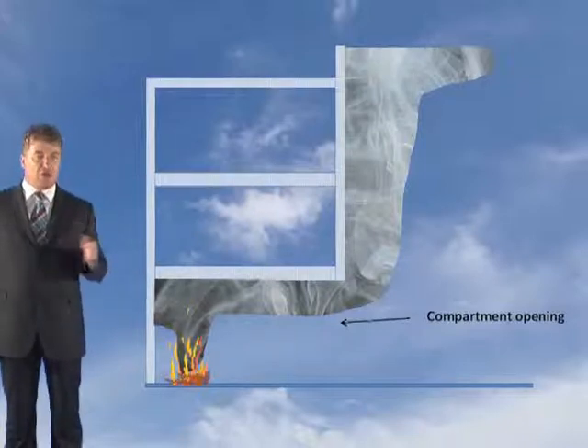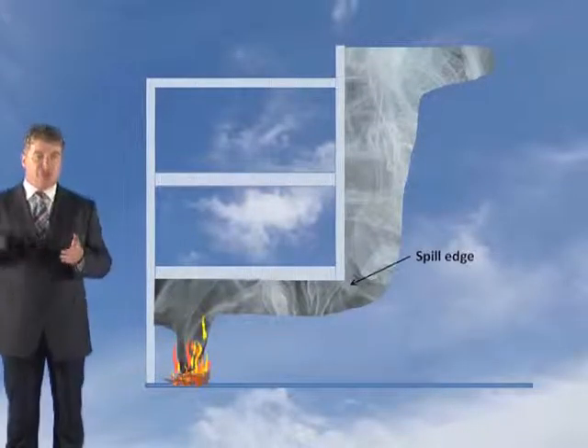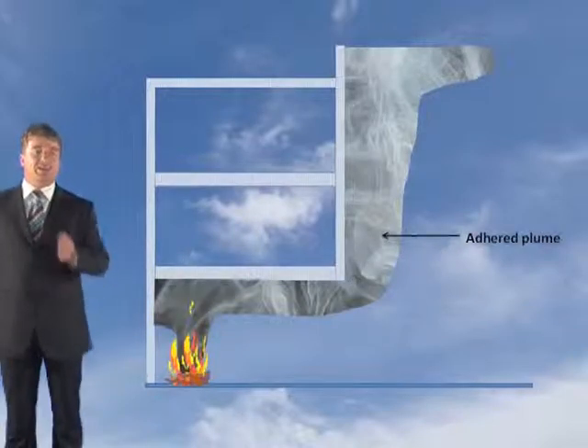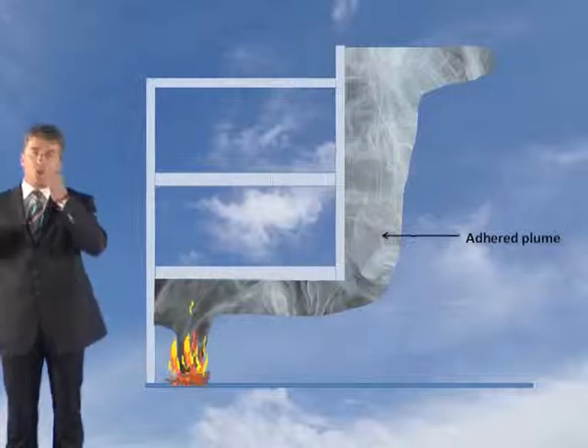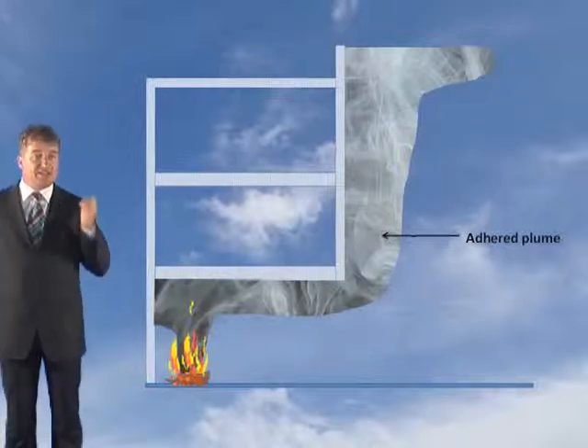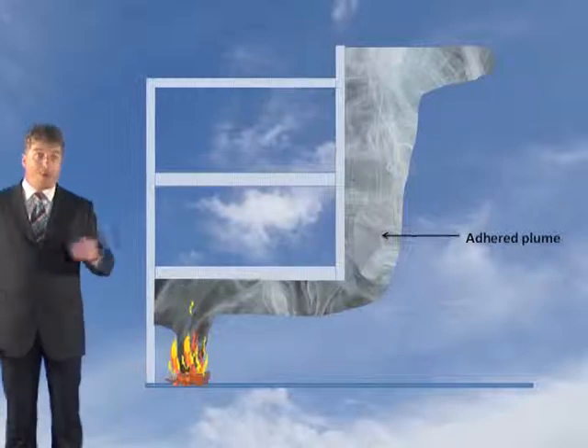Now the smoke layer below the compartment opening will then rotate at the spill edge — in other words, it comes out of the opening — and this plume will then adhere to the vertical wall as it rises, so it won't be entrained from the back. This type of plume is also known as a single-sided spill plume, or an adhered plume.